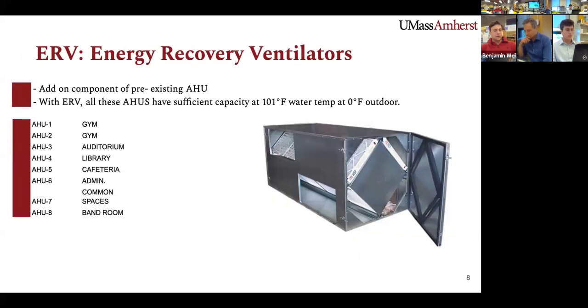These are very easy to install. They're securely mounted right on the air handler, and once mounted, the technician will connect the ERV's ducts to the existing ductwork of the air handler unit. Very easy to install, and the air handlers listed are great candidates for adding ERVs.